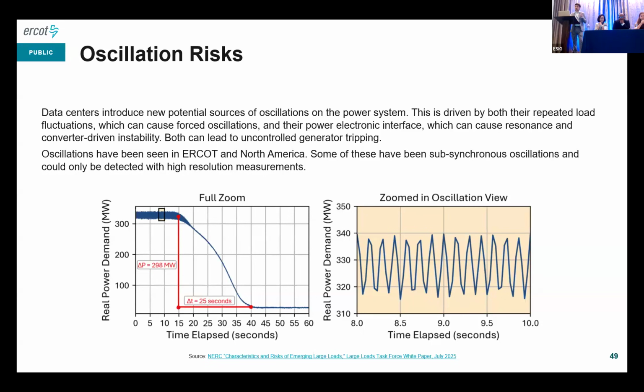Now, we've seen these in North America, in ERCOT, we have seen subsynchronous oscillation. One thing I'll leave you with is that originally, PMU measurements were not always enough to detect it. You needed good DFR data and high quality measurements. There's a great report that just came out from PNNL on PMU adequacy for large data centers, so I'd recommend you all look at that.